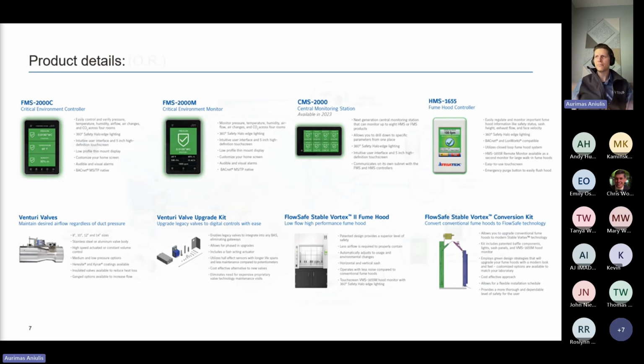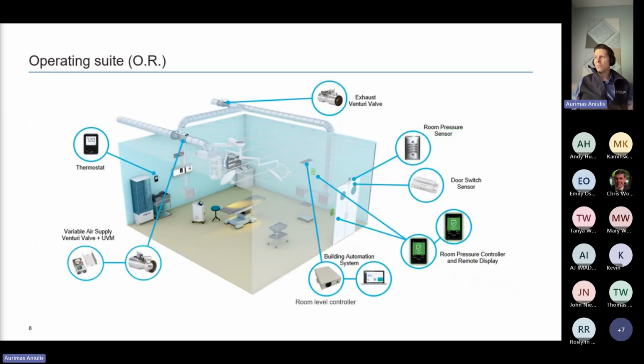So starting with some of the more basic application of critical environments is, of course, our operating suite, the most critical room in the hospital. That's where patients are open, exposed to the ambient conditions in the space. And that's why we want premium, pristine, clean air being pumped and dumped into that space and pushing all the potential debris and any contaminants in the air into the adjacent spaces, through the door cracks, through the drop ceilings and whatnot, so that nothing can land on the patient.